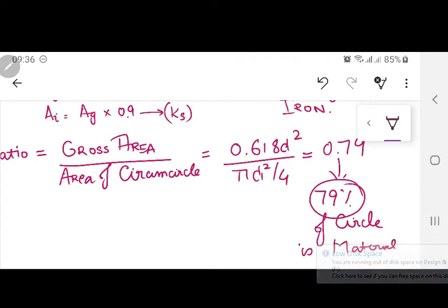That material can be iron, and that material can also be the silicon resin that is between the laminations. So you can see the remaining 21% is a huge area that is being taken up. But again, this 21% is not fixed. It is dependent upon that 0.9 stacking factor. It can be even less than that if you have a 0.95 stacking factor.